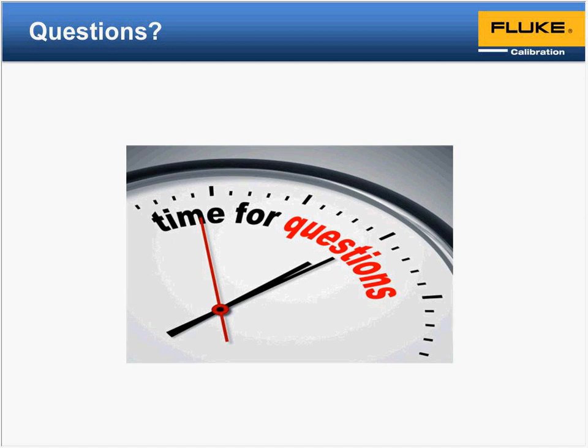The next question is, after an adjustment, how do you verify whether the meter is accurate or not? That's again going to be with the as left data. So you take your as found data, you make adjustments, and now you're going to read the same temperature data. That as left is where you're re-verifying that the adjustment is correct. Based on the as found data, you say, okay, I'm out, so I'm going to compensate 0.2 degrees up or down, and then I'm going to go back to that data point and make sure that where I saw 0.2, I'm now seeing 0. Another person asks about it, and yes, it's always good to do more in calibration.